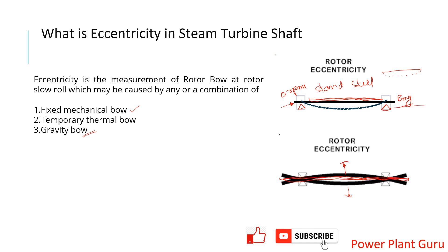That is why it is very important to check the rotor eccentricity while you are starting up your machine. This is not very critical when the machine is already running, because then the rotor is most of the time in a stable condition. It is only when you are starting the machine that eccentricity comes into the picture.